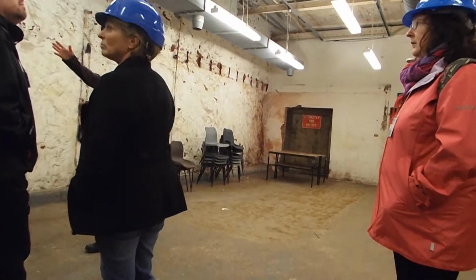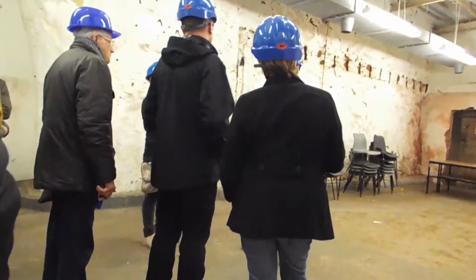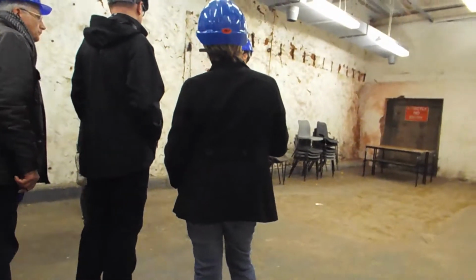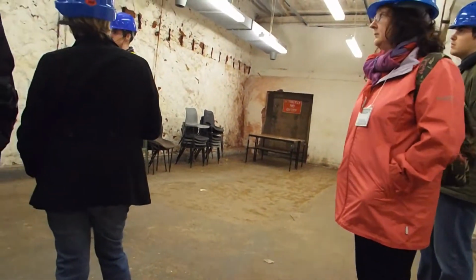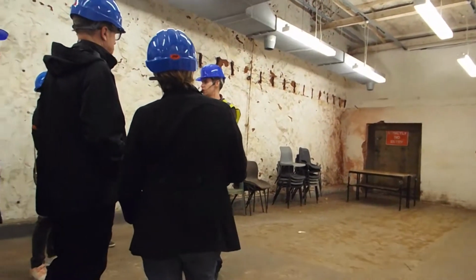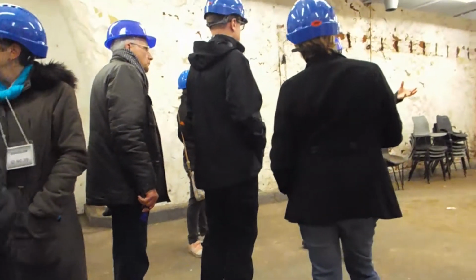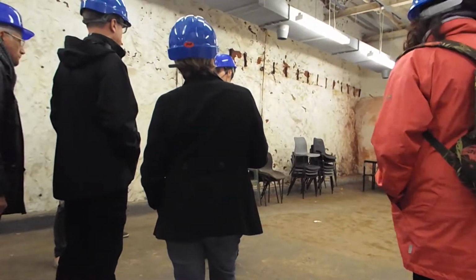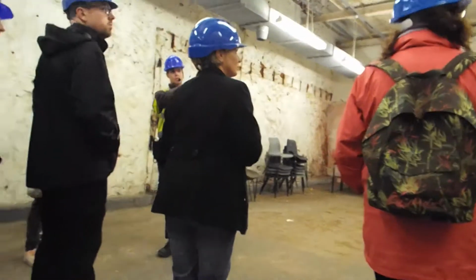Yeah, that'll be it. And the reason for the double doors is before we had flaps, like going into a fridge in a supermarket, and it did alright, but it just wasn't effective. In the 1980s, that was bricked up, so they really didn't have any issues of having the efficiency of the air conditioning unit. They just bricked up the areas they didn't need. Obviously, we need people to be able to go to and from, so we've got doors in places, and hopefully that will just make it so we're not pulling in the warm air of the older complex into the regional headquarters, which is what we're going to be doing for the museum. Once we put in doors everywhere and sealed it all off, then it's just going to become even more efficient as well.